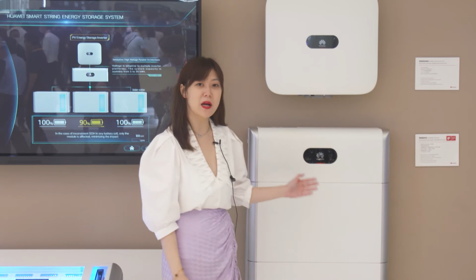Here is the Smart String Energy Storage System, the flagship product Luna 2000 battery. It was designed with the residential scenario in mind. It is 1.3 meters in height, and each module is 5 kWh. Modular design allows customers to flexibly configure the battery capacity from 5 kWh to 10 kWh to 15 kWh. The system supports 2 batteries connected in parallel, meaning the energy storage battery capacity can be extended to 30 kWh. Smart string architecture allows 30 kWh capacity which you can rely on 24/7.